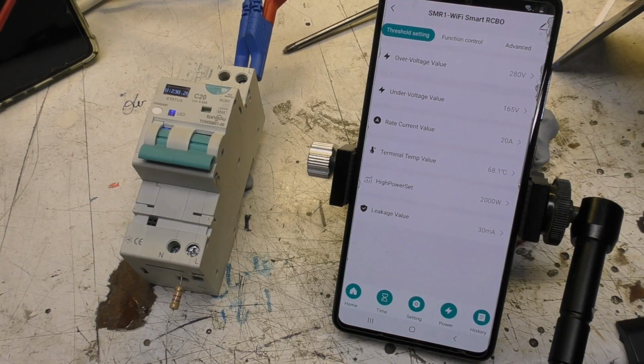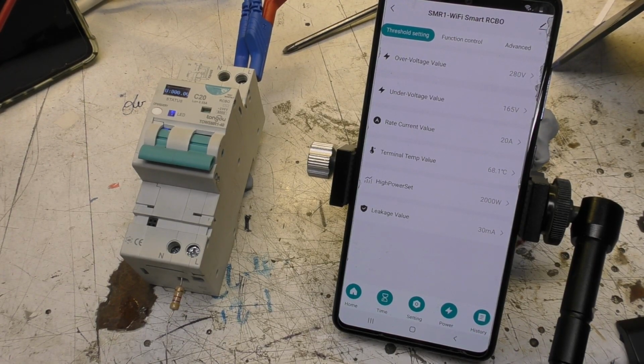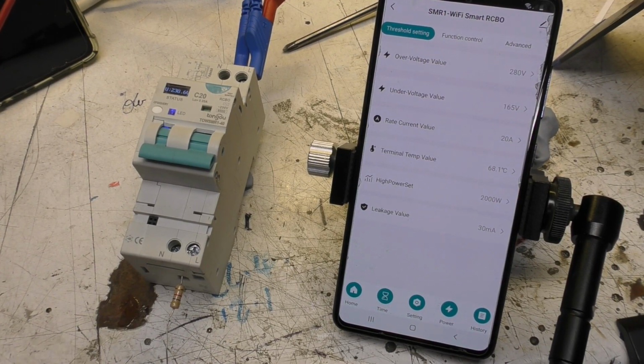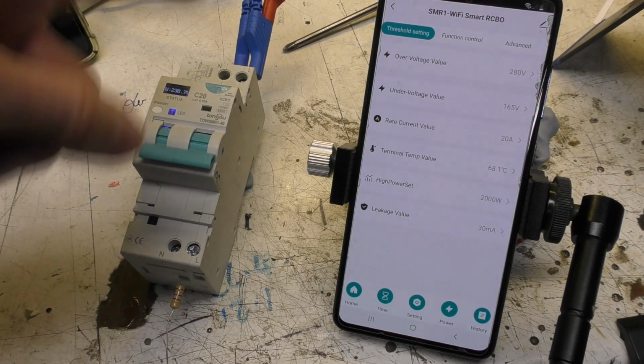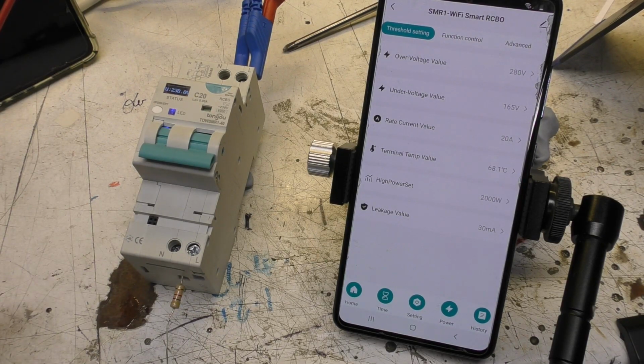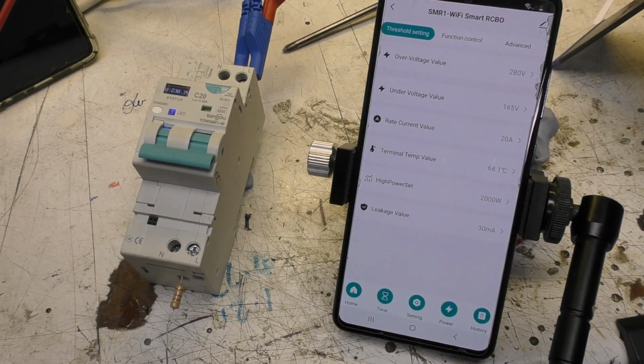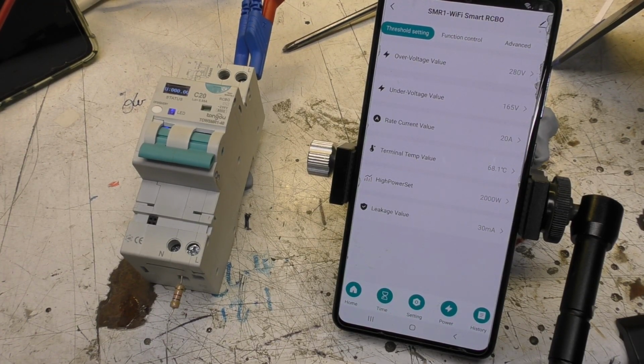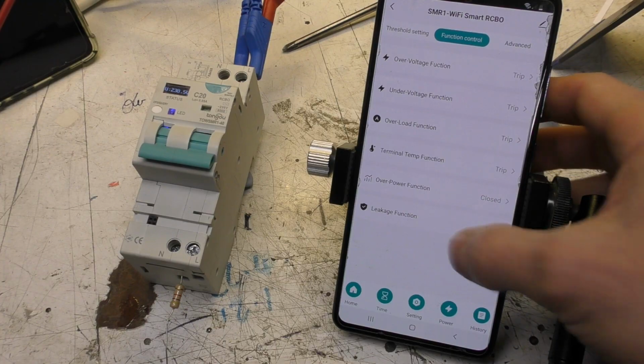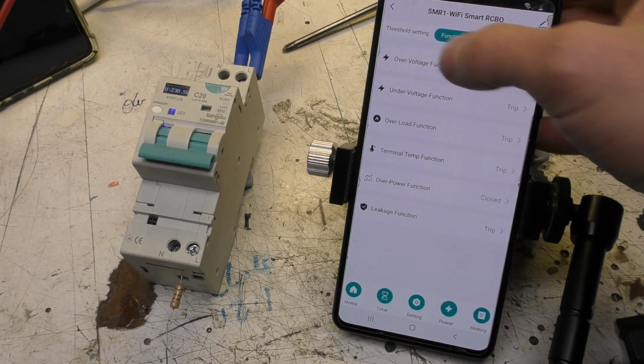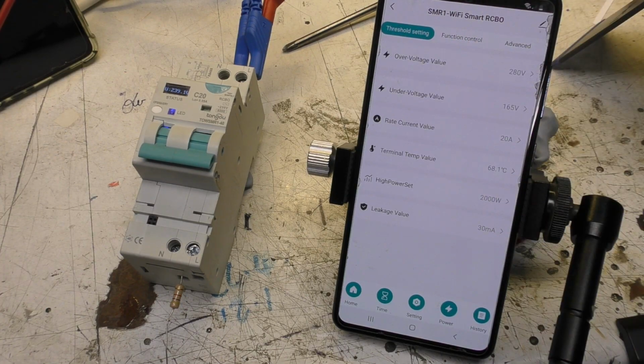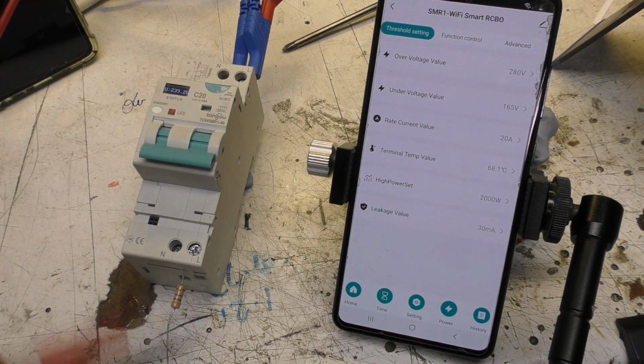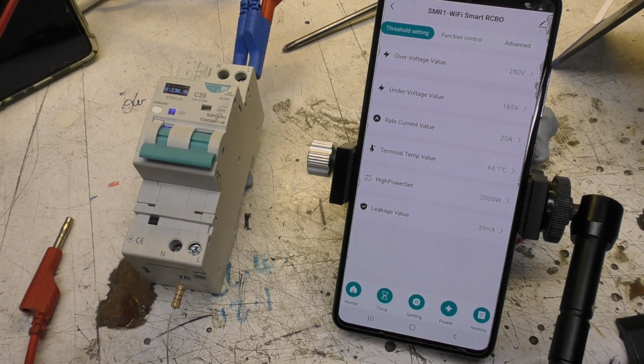Okay, let's take a quick look at earth leakage RCD functionality. I've got a 4.7k resistor there, which will generate an earth leak of about 50 milliamps. It's just connected diagonally between live in and neutral out, so I don't have any worries about tripping upstream breakers. This is all set to the default values now, so the trip's enabled and the threshold is set to 30 milliamps. So turn it on, trips out straight away. I haven't got the equipment to do part of the normal way of testing these in the UK, which actually measures trip times at various different currents.